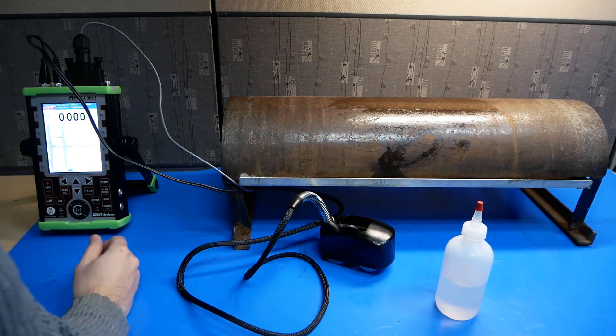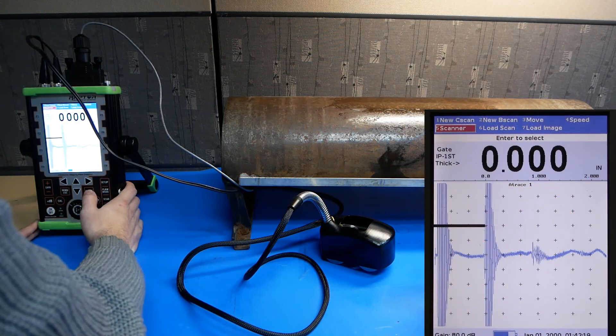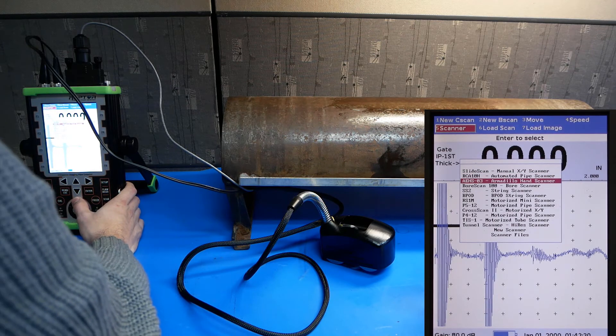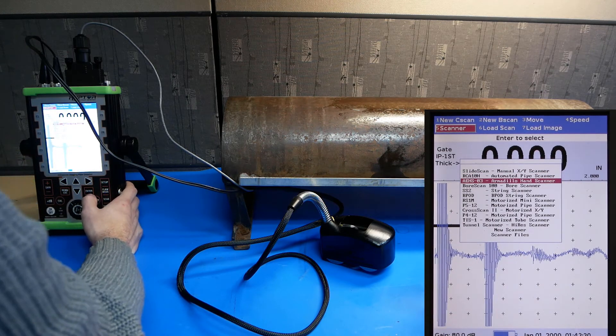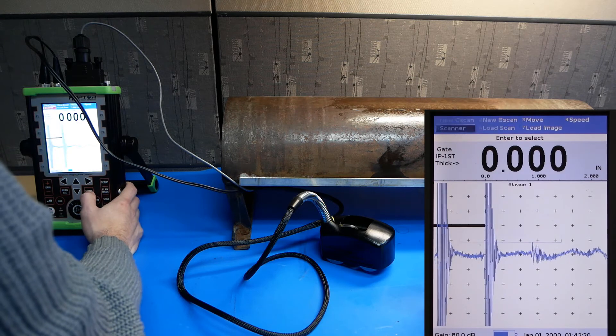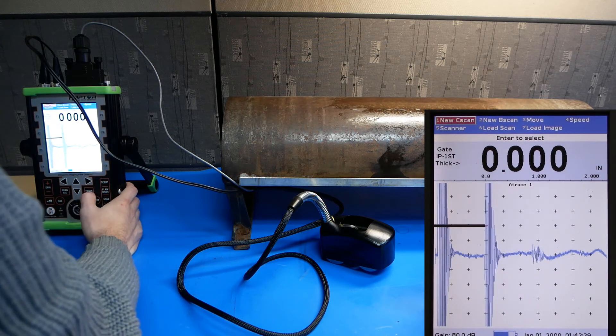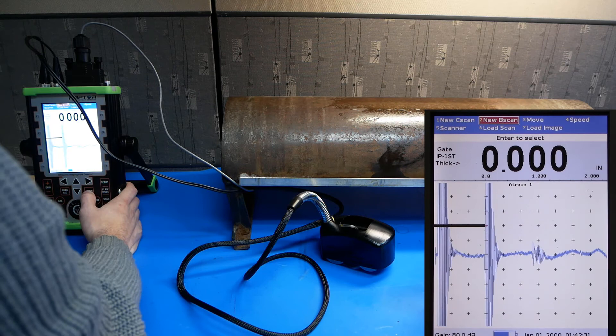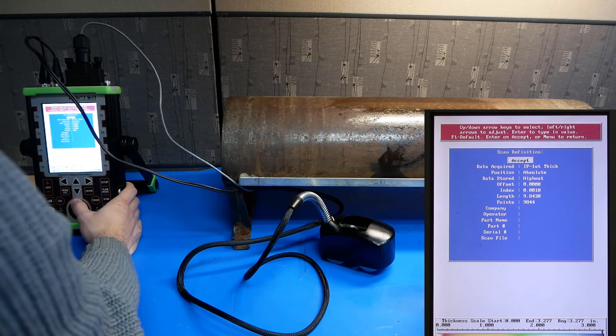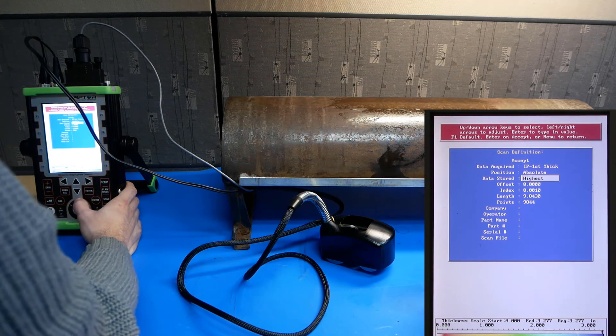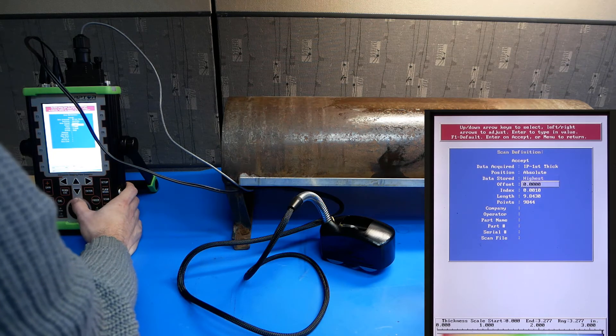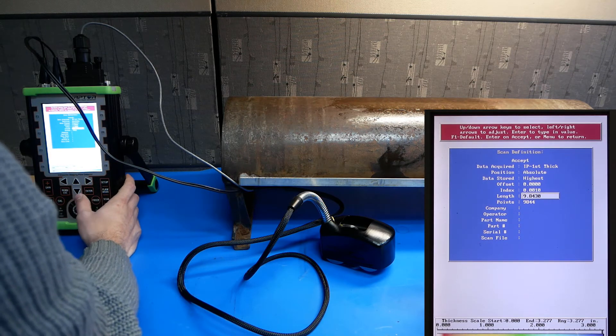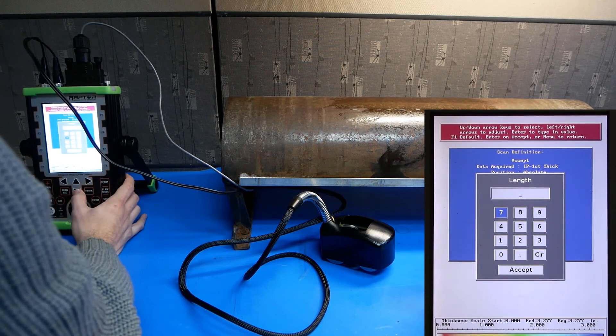Next, go to scanner on your Raptor. Select AEHS-03 for the Armadillo hand scanner. Go to new C-scan or B-scan. We'll do a B-scan in this case. And select the range of measurement. We'll change this to 5 inches.